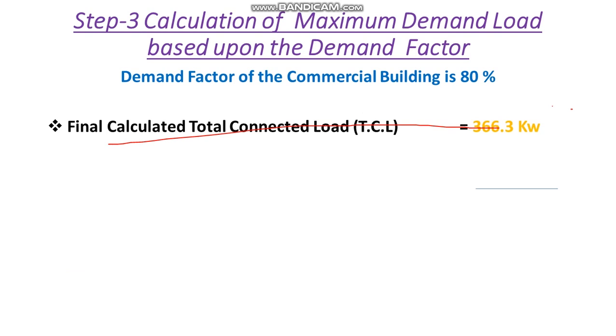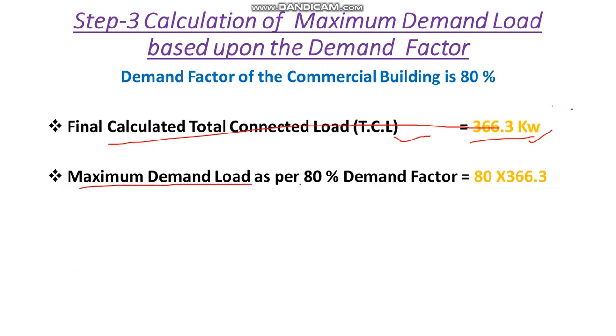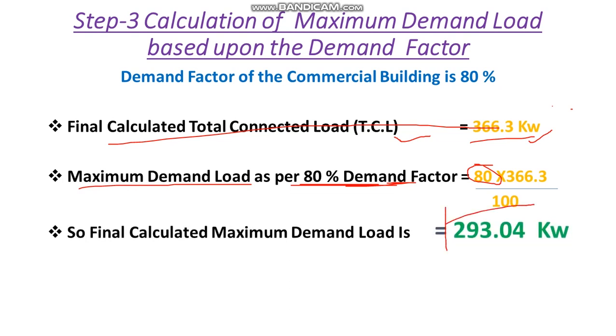We need to size the transformer as per the maximum demand load. Our final calculated total connected load is 366.3 kW, and the demand factor is 80%. So the maximum demand load is 80/100 × 366.3 = 293.04 kW.